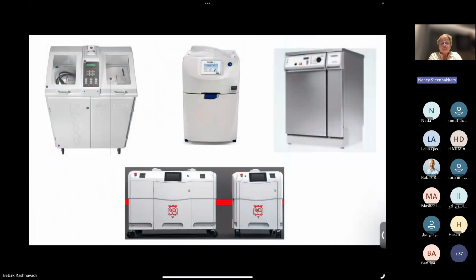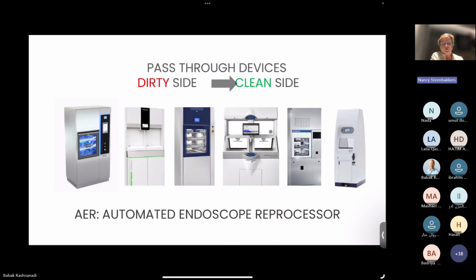As I told you, you have all these magnificent washer disinfectors, and they're all good, but in the end, this is not a magic box. That's something that you have to understand. You cannot skip the manual pre-cleaning steps in your sink and go straight into the washer disinfector, because your result gets worse and worse. So you cannot do that. You have to do the pre-cleaning. And you have to follow, of course, the instructions for use from Olympus, Pentax, Fujifilm, Wolf, Storz, whatever you have. So here again, you have the washer disinfectors with two sides. You have the dirty side and you have the pass-through device. They are very good, but still they are not a magic box. When we were testing those devices, it's a good device, but of course we still have to count first on a good pre-cleaning. Next, please.